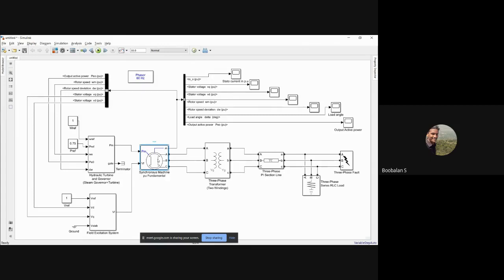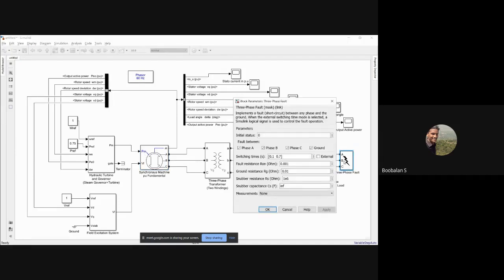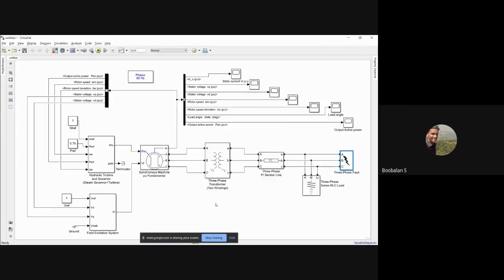In the same way, after 0.1 second, the synchronous generator speed is going to change. Got the idea? This is what we are going to see today. In the period the fault occurs, the synchronous speed and load angle are going to change. Then an automatic and periodic control will bring the system to a stable area. It will force the steam valve to adjust the steam flow, and the turbine is going to be rotated at a different speed. After that it will reach stability, right?